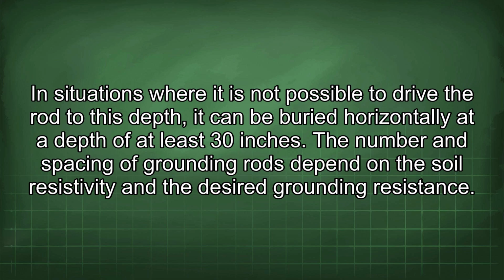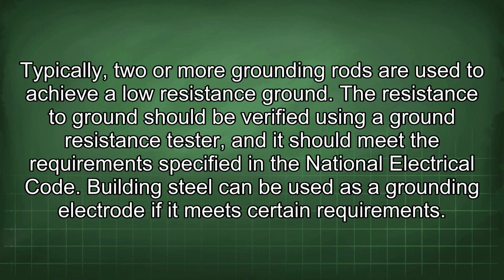In situations where it is not possible to drive the rod to this depth, it can be buried horizontally at a depth of at least 30 inches. The number and spacing of grounding rods depend on the soil resistivity and the desired grounding resistance. Typically, 2 or more grounding rods are used to achieve a low resistance ground.